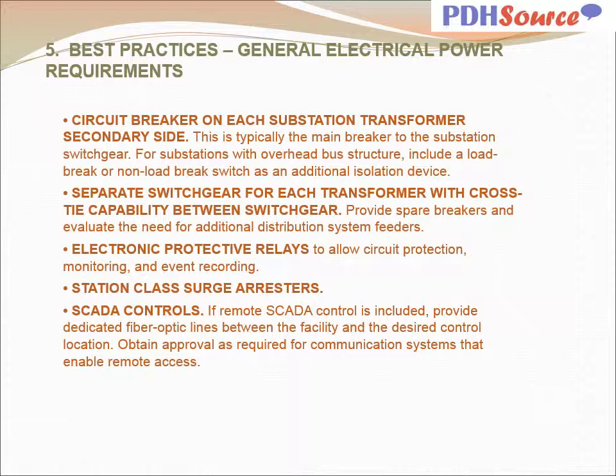Electronic protective relays to allow circuit protection, monitoring, and event recording. SCADA controls. If a remote SCADA control is included, provide dedicated fiber optic lines between the facility and the desired control location. Obtain approval for communication systems that enable remote access.